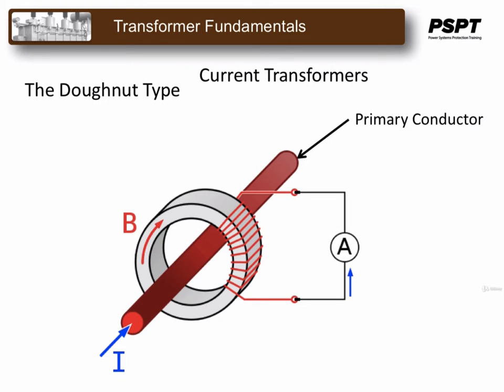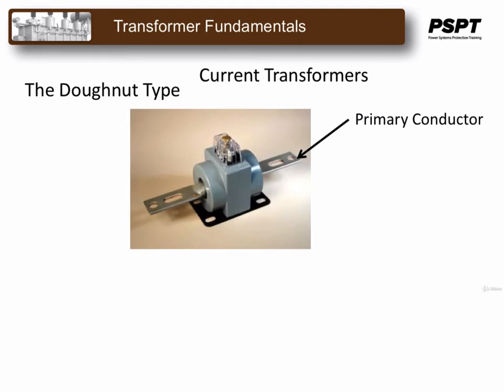The donut fits over a conductor, bushing, or bus bar, which constitutes the primary having one primary turn. The secondary is wound around a toroid core, which is usually made up of laminated iron that concentrates the magnetic flux and forces it through all of the secondary turns. Some donut CTs come with the primary conductor incorporated in the CT itself, and connections are made by bolting to the primary lead.